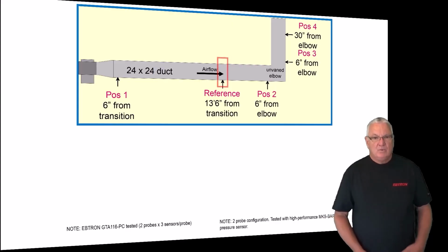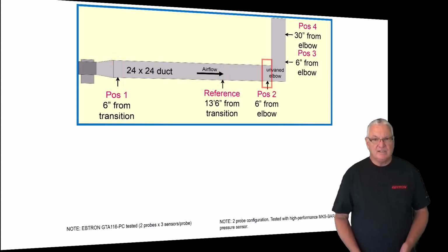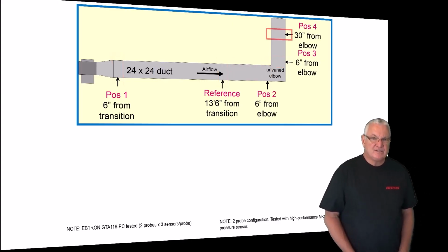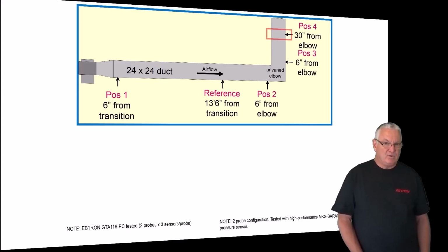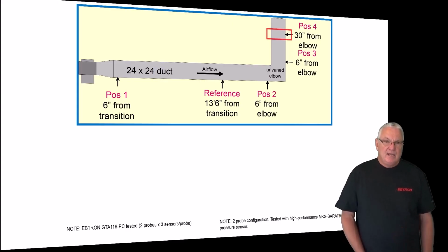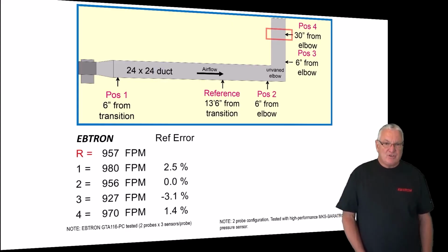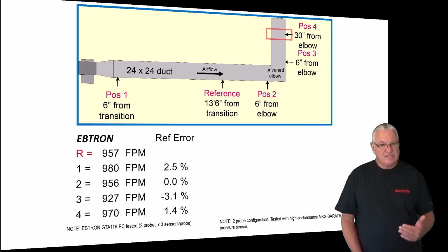Okay, so we'll take off our flow meter and we'll put it in a reference position, which is a really good straight run of duct, and we'll move it to really bad locations that we wouldn't recommend. But anyhow, when we show, for instance, how the EBTRON works, and this is typical, it varies a little bit from time to time, but not much, you'll see that as we go from these different positions, we do get some variation in the flow, but it's very small.